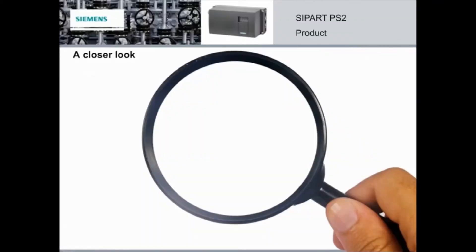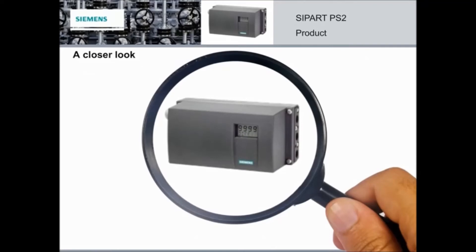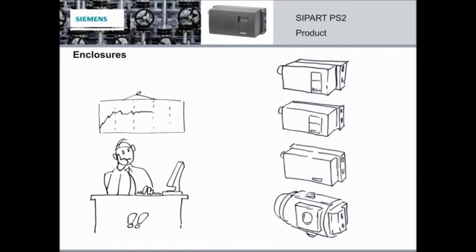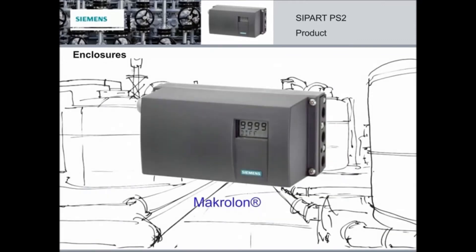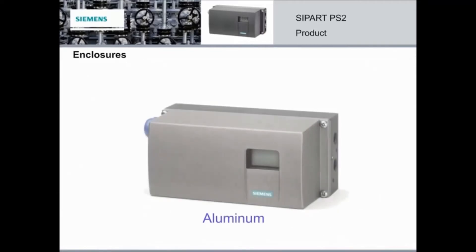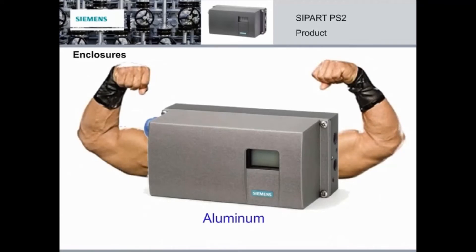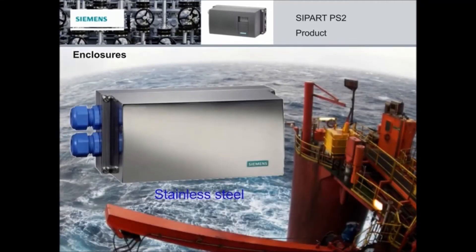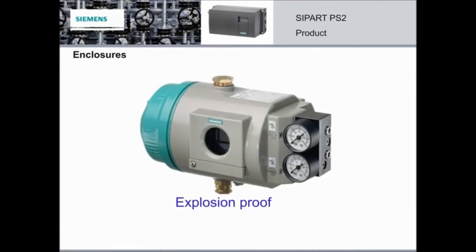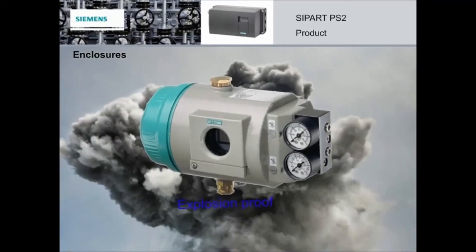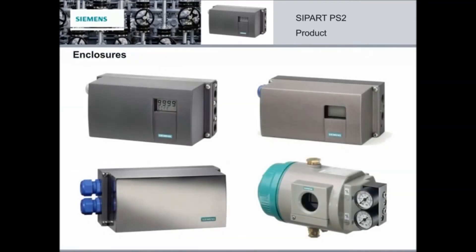When it comes to precision control of valves in different industries and applications, the SIPART PS2 is the first choice. So let's take a closer look at the main benefits of the PS2 that were introduced in the movie to see what exactly makes it number one. Although small in size, the SIPART PS2 is a robust instrument with four specially designed enclosures for aggressive environments. The standard Makrolon enclosure is used for about 80% of the applications. The aluminum enclosure is an option for tougher applications. The stainless steel is designed for salty environments, making it ideal for any application close to the sea. And the explosion proof enclosure is designed specifically for explosive areas. No matter what atmosphere surrounds your SIPART PS2 positioner, you are perfectly equipped for all occasions.